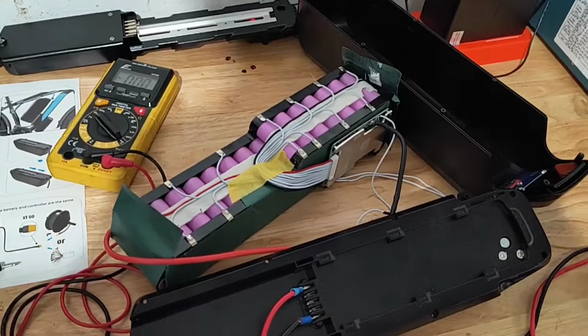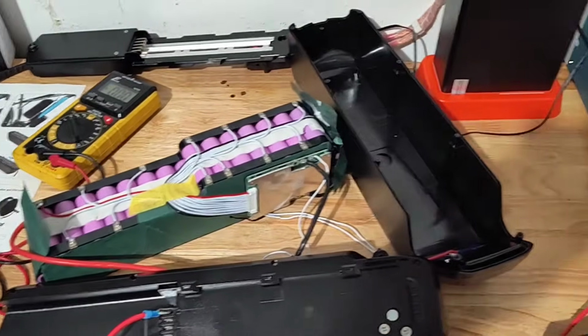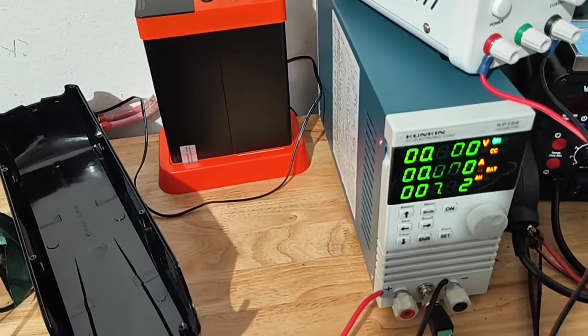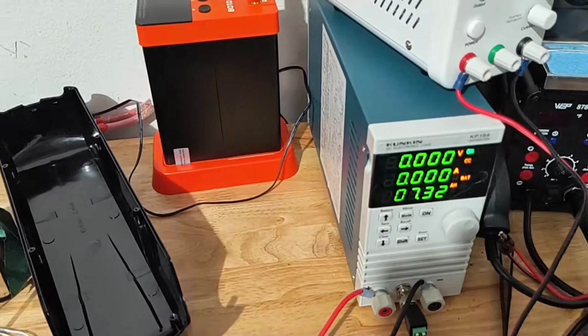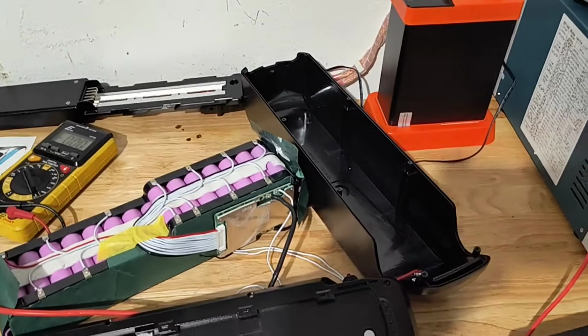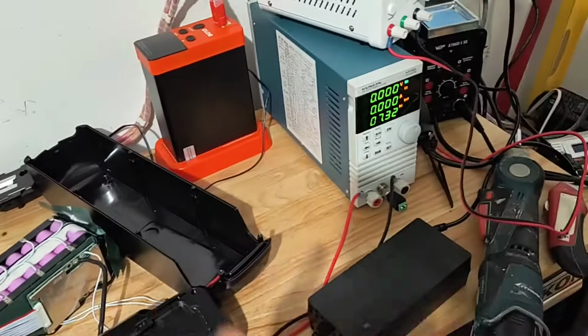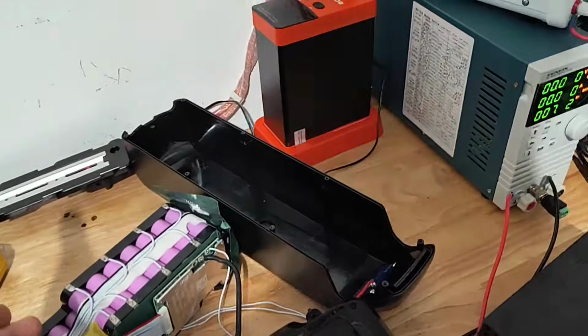Alright, it's the next morning and the discharge test is done. We ended up with 7.32 amp hours, not quite the 10.4 they were claiming - that's a bit of bad news. For the good news, it does have over-discharge protection - it actually shut off.